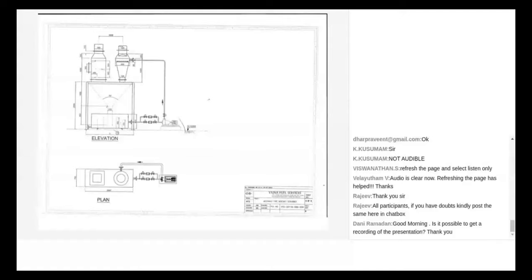Otherwise, the moisture will go to the chimney, and the chimney will start oozing out water, and people don't want that kind of hassle. When you ask what's the issue, well, you could just keep the flange at the bottom of the chimney open and let water come out, but that creates a muddy situation, and everybody says this design is not good because it makes a muddy space where everyone's shoes get dirty. So instead, you give a mist eliminator, which is a baffle type.